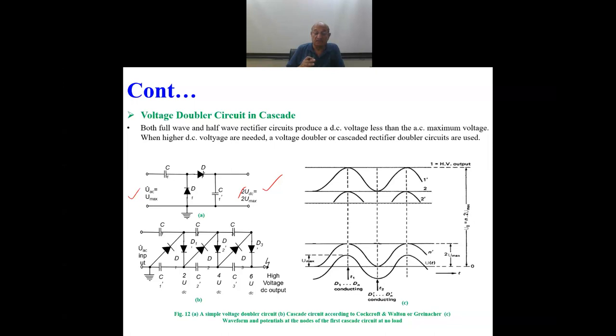And when you connect a number of voltage doubler circuits in cascade, one after the other, in series, this diagram is showing you the voltage doubler circuit in cascade. So as you can see here, you are applying an AC input here. The peak value is what we are working with, because it is converted into the DC maximum value. And at this point, these are the stage capacitors, C1 prime, C2 prime, and C3 prime. Three stages are shown in cascade.